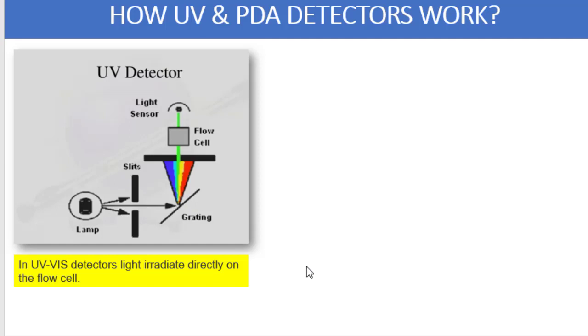The flow cell is the compartment through which either mobile phase or the sample gets transferred. When the sample enters into the flow cell it can absorb the light which is falling onto it. Whatever light absorbed will be measured by the light sensor or the detector.